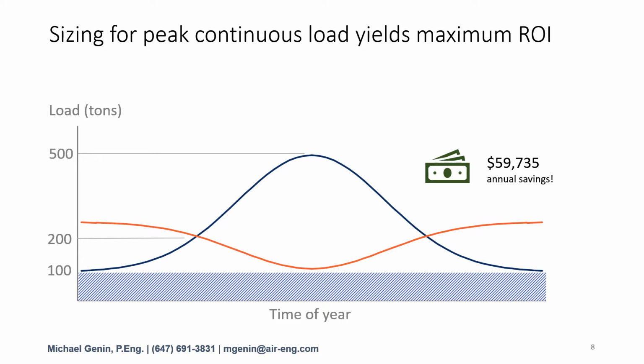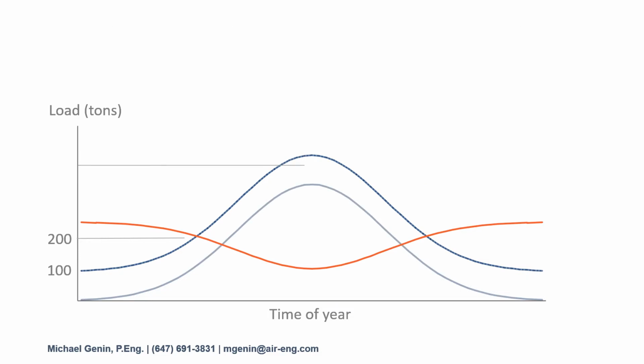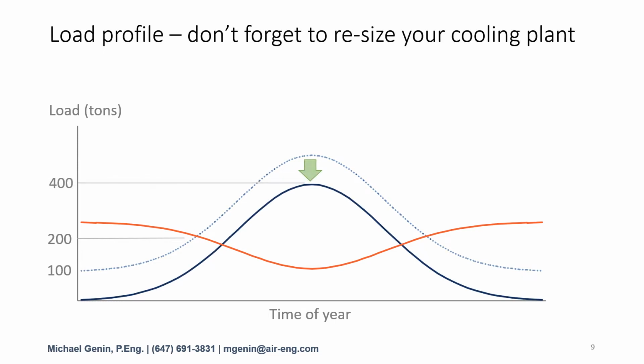If we implemented a 100-ton heat recovery system in this instance, the remaining cooling load profile could be reduced from 500 tons down to 400 tons. This remaining 400 tons of cooling can be done with a downsized conventional chiller. This is because we can rely on the minimum base cooling load of 100 tons, which has been offset by the heat recovery chiller. It's best to size the cooling system as a whole and take these considerations into account in order to achieve the greatest ROI.